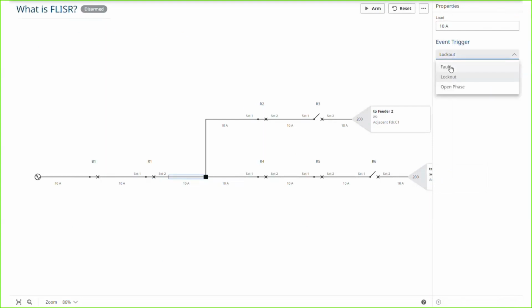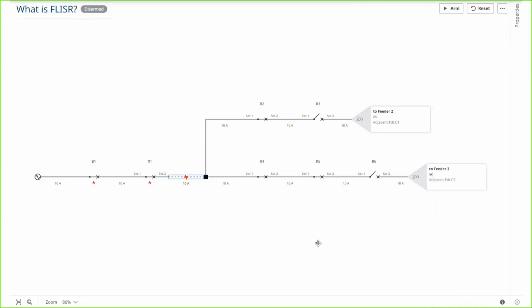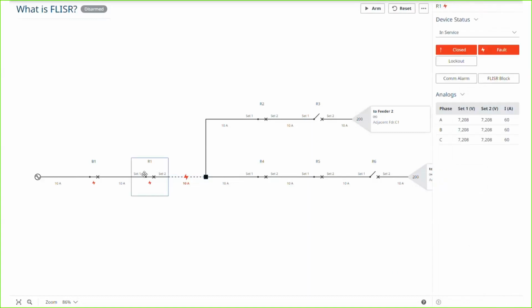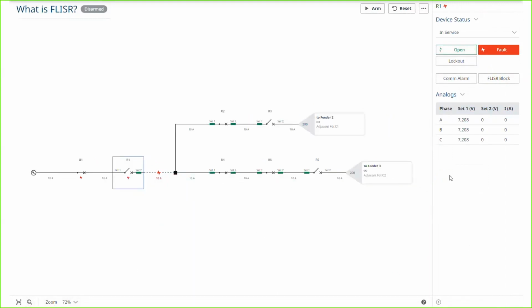So what I'm going to do here is apply a fault near this line tap. When that happens, there's an overcurrent fault, recloser 1 will see it, breaker 1 will see it, and the recloser will open. Again, this would simulate a reclosing shot, right? The recloser will open and then it will close, and then it may open again, and then it will close. Eventually, if the fault is permanent, that recloser will lock out.